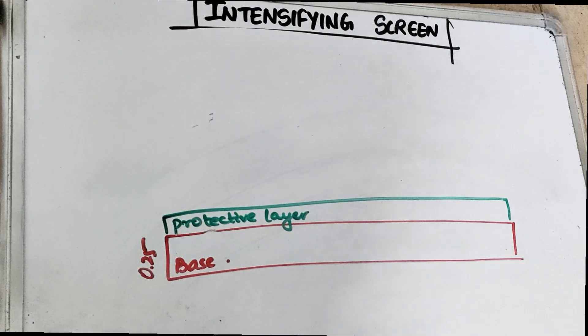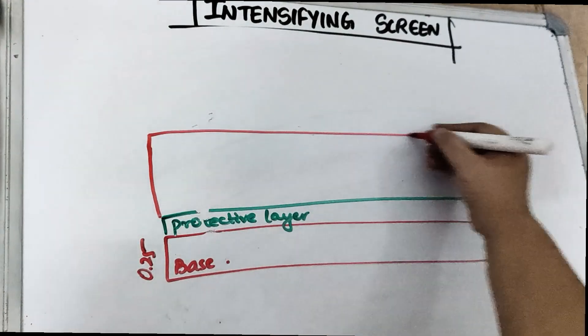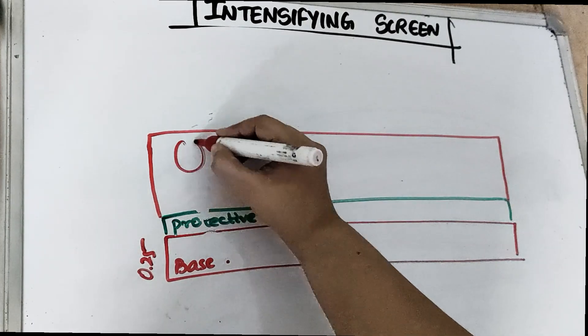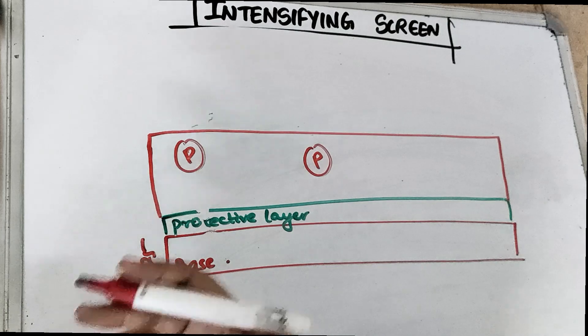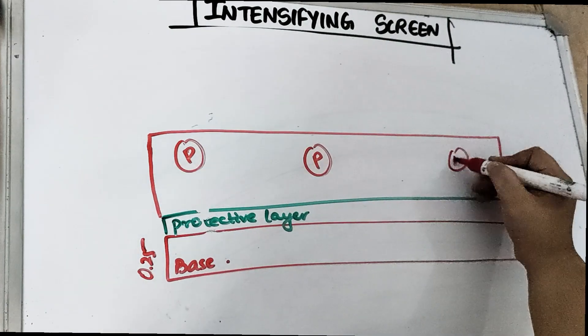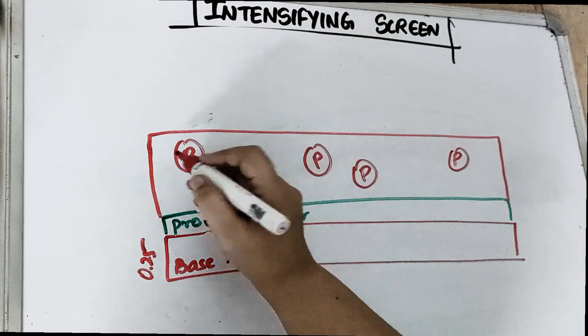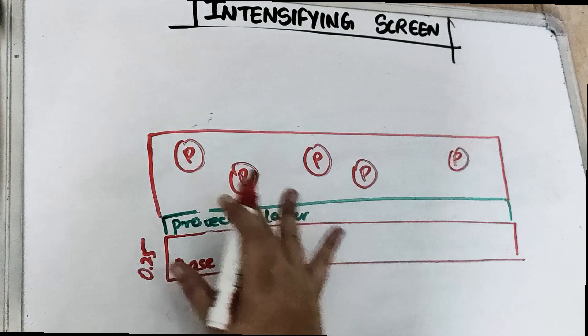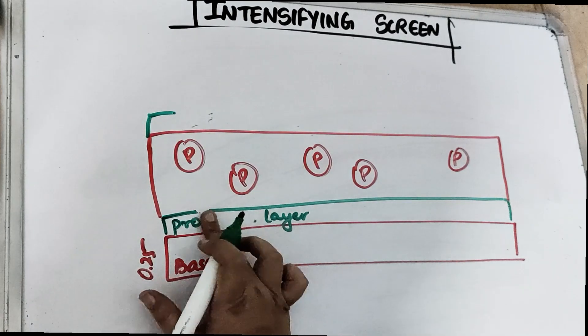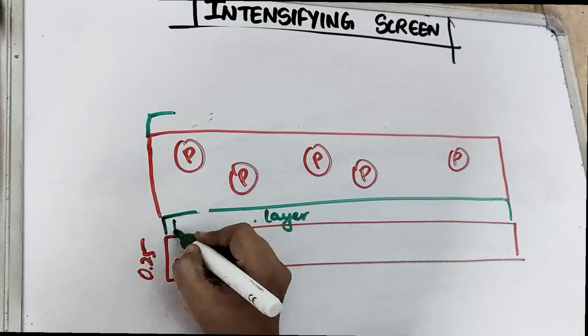Above the base, we have the phosphor layer. The phosphor crystals have the property of luminescence — they are going to convert the x-ray radiation into light radiation. These phosphor crystals are floating, they are swimming inside a matrix which is made up of plastic — P for plastic, P for phosphor, very easy to remember. Above the phosphor layer, we have a protective layer. And below the phosphor layer, there is what we call the reflecting layer.